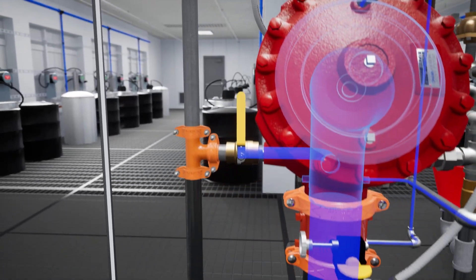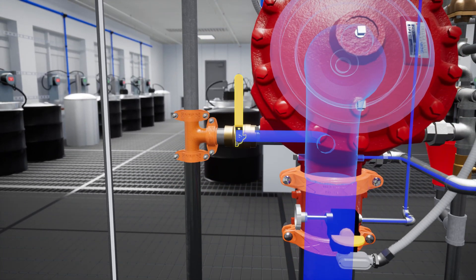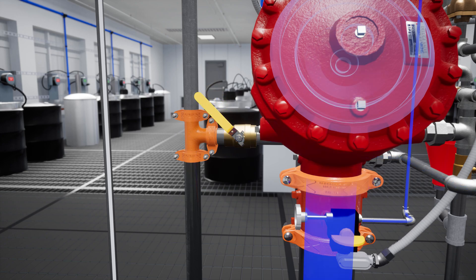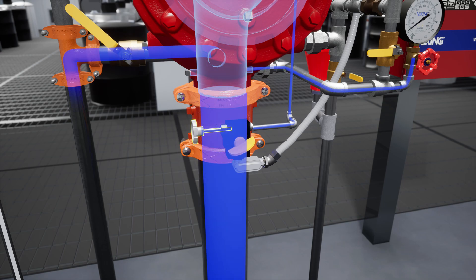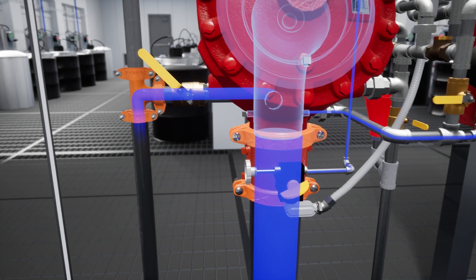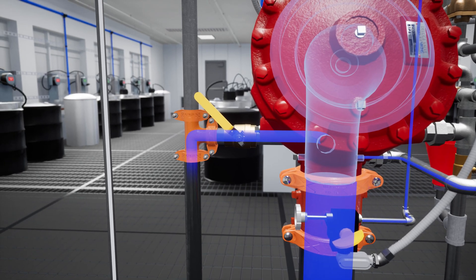Once priming pressure is reestablished in the priming chamber, slightly open the flow test valve. Then slightly open the water supply control valve. Once flow has been established, close the flow test valve completely.